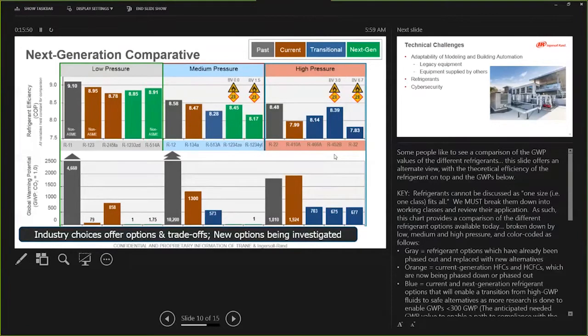And then finally, R32, which is getting a lot of press, has a little bit lower efficiency than 410A as a drop-in refrigerant, actually a higher burning velocity than 452B, and a lower minimum ignition temperature.